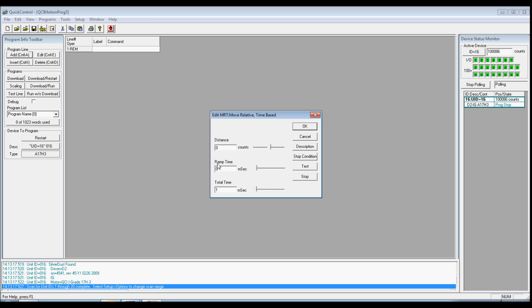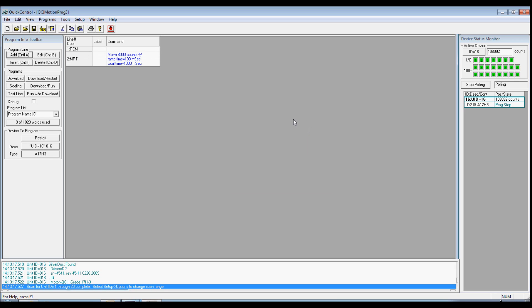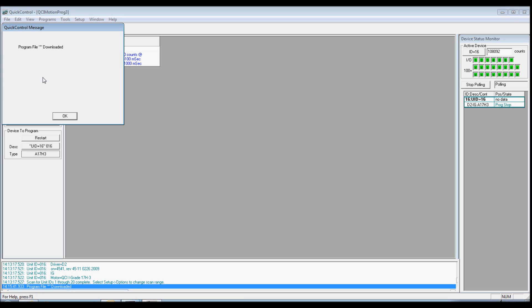Edit the move data: 8,000 counts, 100 millisecond ramp time, in 1 second. Press Test to preview the motion. Press OK to add this command to your program. Under the Program Info toolbar on the left of your screen, press Download and Restart. Quick Control will download your program to the servo's non-volatile memory. It will then restart the controller and go 8,000 counts in 1 second. You can press Restart to cause the program to execute this move every time the servo powers up.